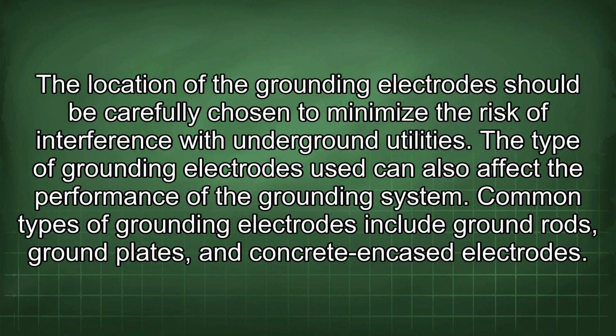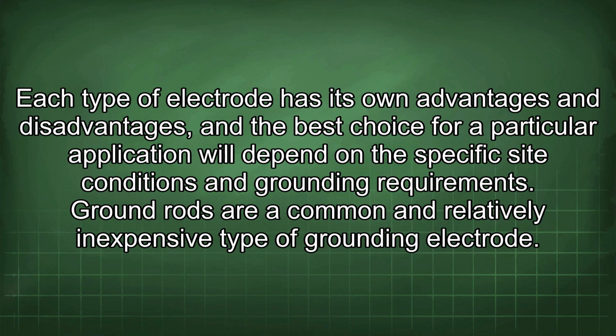The type of grounding electrodes used can also affect the performance of the grounding system. Common types of grounding electrodes include ground rods, ground plates, and concrete encased electrodes. Each type of electrode has its own advantages and disadvantages, and the best choice for a particular application will depend on the specific site conditions and grounding requirements.